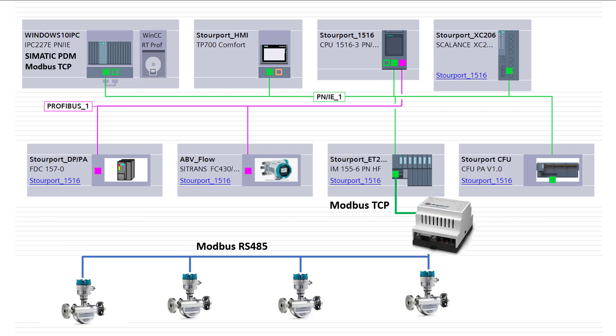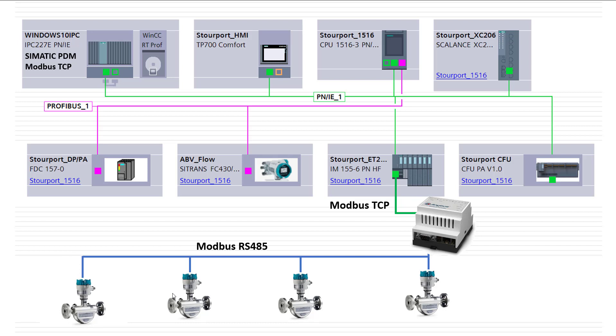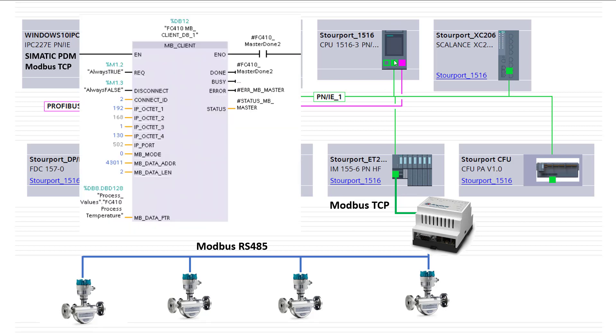The solution that I find works the best is to use a Modbus 485 to Modbus TCP converter. And yes, we may have PROFINET comms on this green cable, but the port for Modbus TCP port 502 is still supported. And the beauty of this device—so we're looking at an Anybus device from HMS—it can have up to 8 masters connected on the Modbus TCP without affecting the Modbus 485 comms. So it will route that traffic for you, and the TIA portal block, the MB client block, will talk to your instruments and bring your process values back.